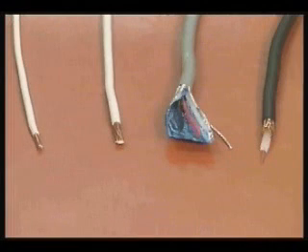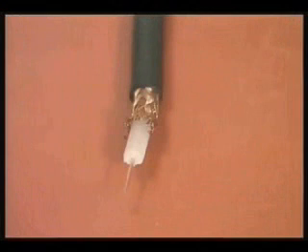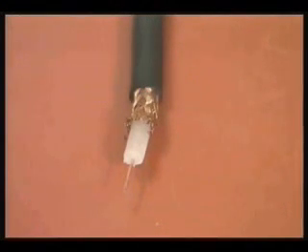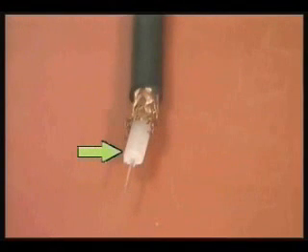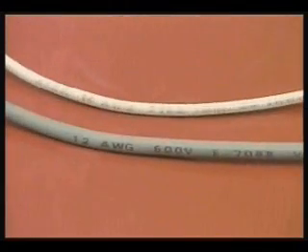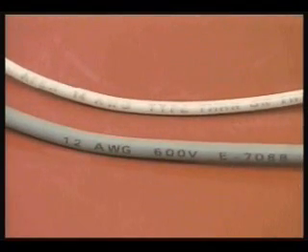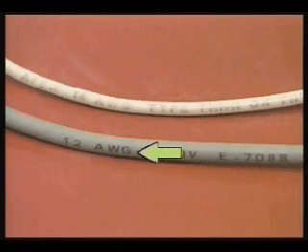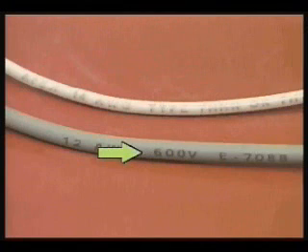Coaxial cable is shielded cable that carries low voltage signals. In addition to a jacket and braided shield, coaxial cable has a dielectric and insulation covering the conductor. The amount of current a conductor can carry is determined by its gauge or size. The wire gauge and voltage must be marked on the insulation. Voltage ratings are determined by the amount and type of insulation.